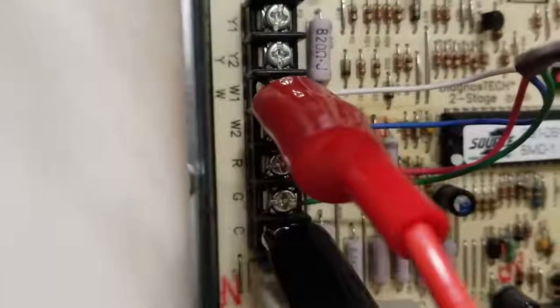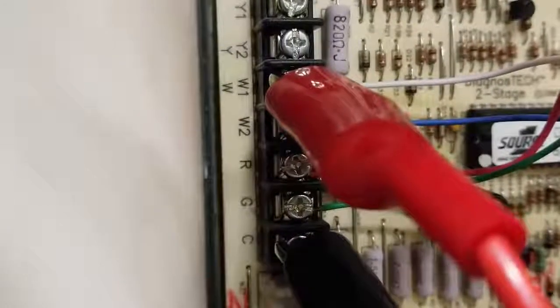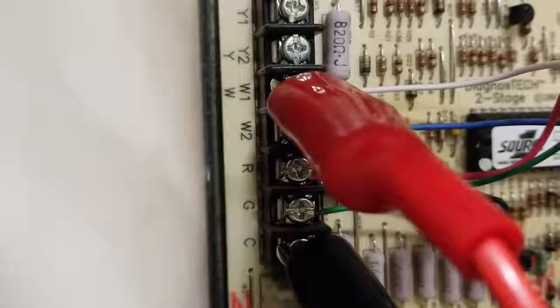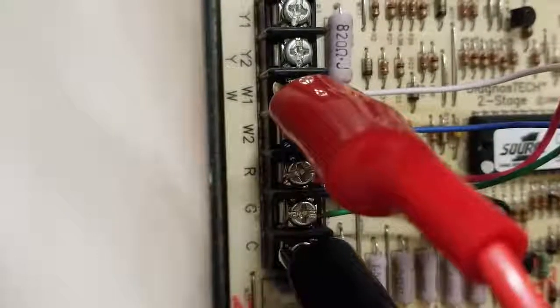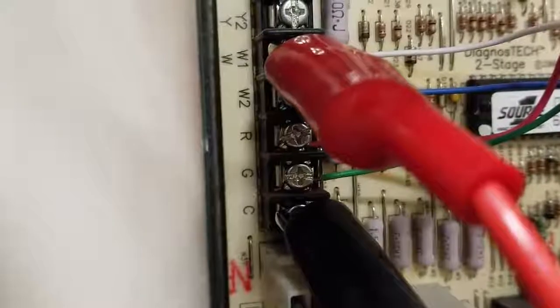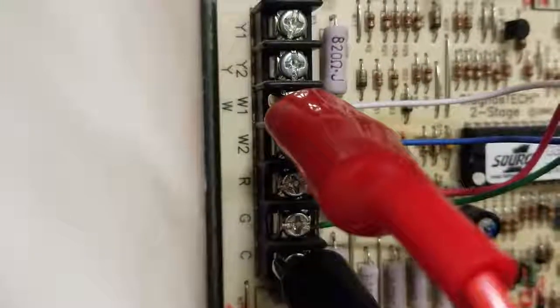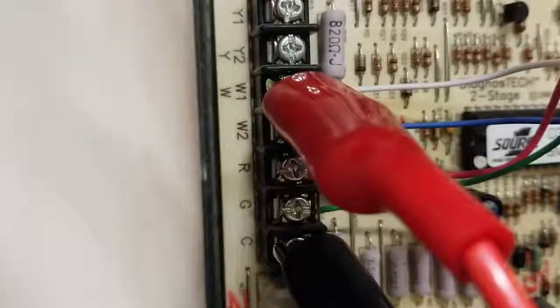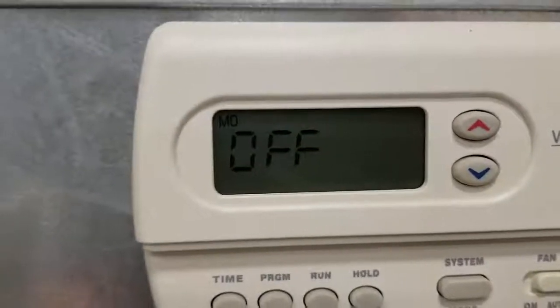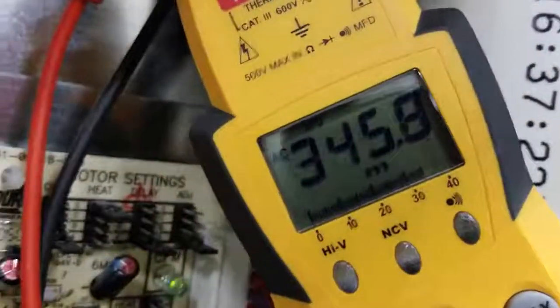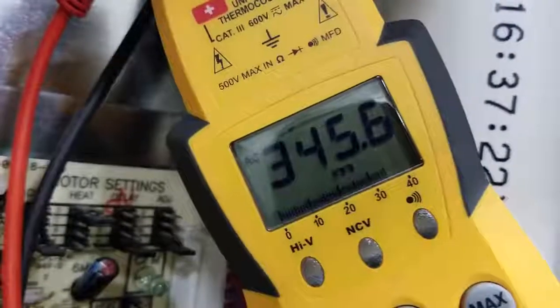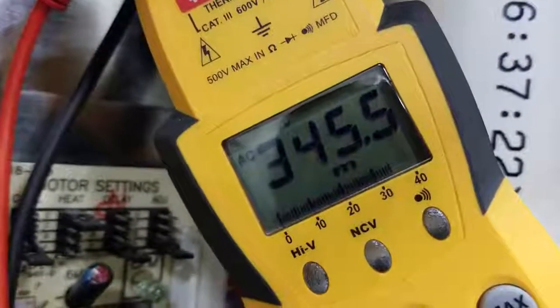So right now I've got my alligator clips hooked on the W terminal, which is universally the heating terminal. When there's a call for heat, that terminal is energized. So power goes from R through the thermostat and back to the W terminal to tell the furnace, hey, I need heat. Okay. Right now the furnace is off. So come up here to the thermostat. You can see it's off. There is no call for heat. So right now we have basically no voltage. We're showing 345 millivolts, which is significantly less than 1 volt, and that's just feedback through the circuit board. That's common.